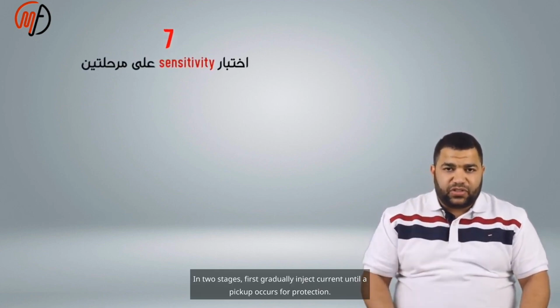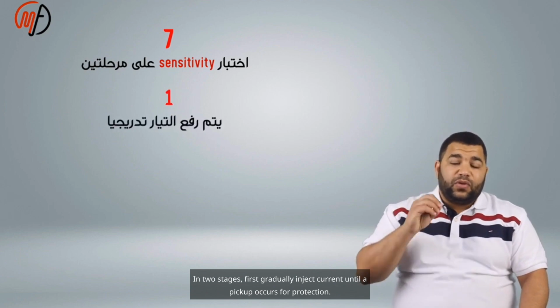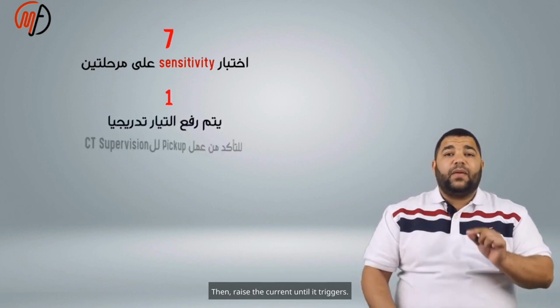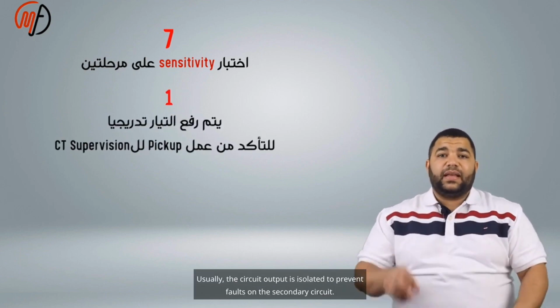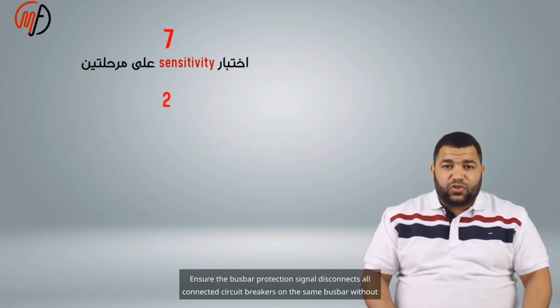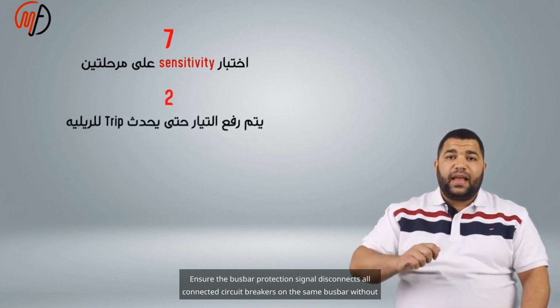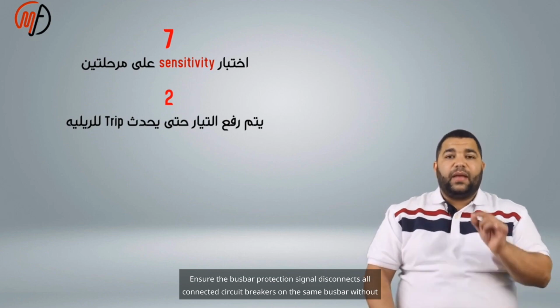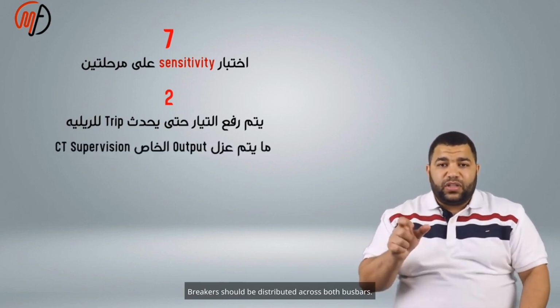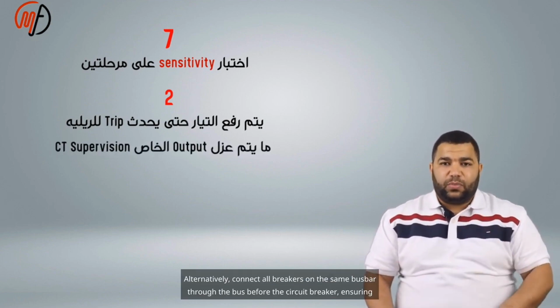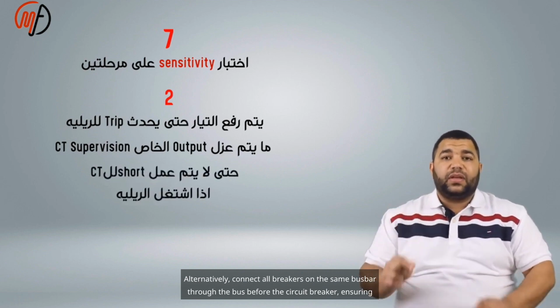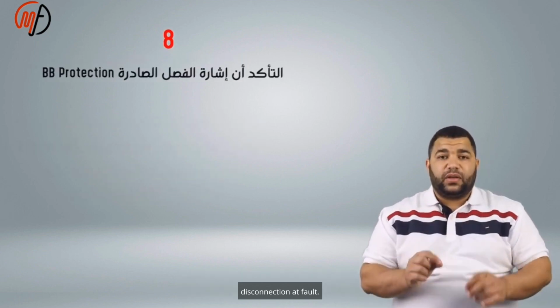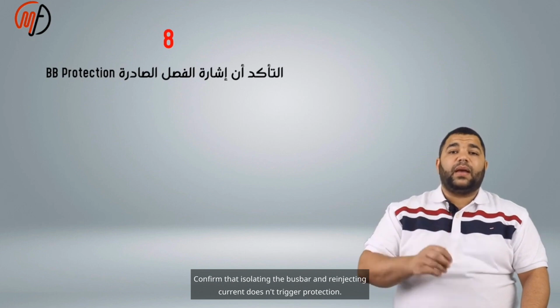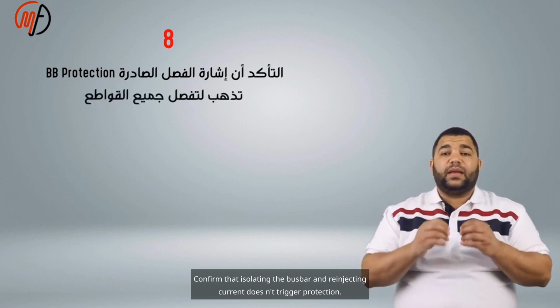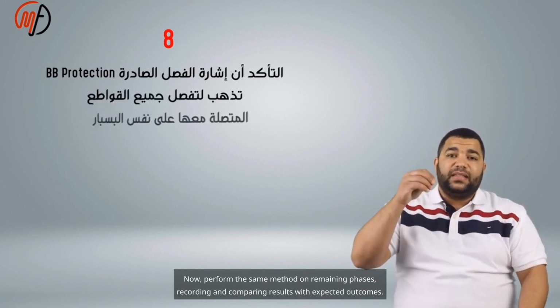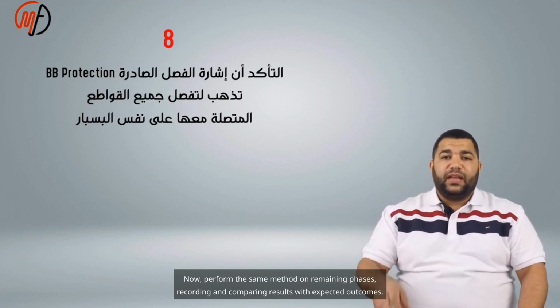In two stages, first gradually inject current until a pickup occurs for protection. Then raise the current until it triggers. Usually, the circuit output is isolated to prevent faults on the secondary circuit. Ensure the bus bar protection signal disconnects all connected circuit breakers on the same bus bar without affecting others. Breakers should be distributed across both bus bars. Alternatively, connect all breakers on the same bus bar through the bus before the circuit breaker, ensuring disconnection at fault. Confirm that isolating the bus bar and re-injecting current doesn't trigger protection. Now perform the same method on the remaining phases, recording and comparing results with expected outcomes.